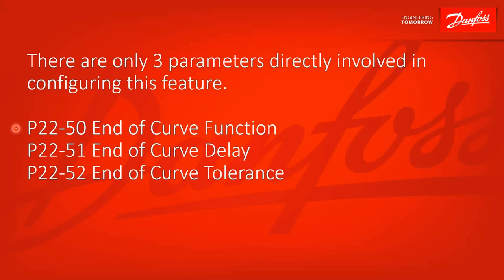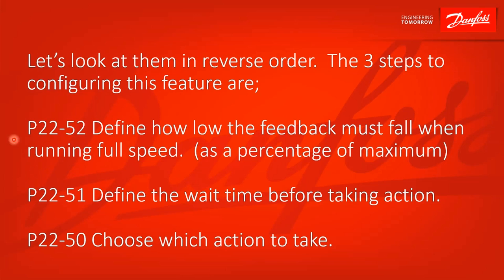You've got parameter 22-50, that's the end of curve function. What do you want the drive to do in this situation? Parameter 22-51 is the end of curve delay. How long do you want the drive to be in that condition before taking that action? And then 22-52 is the end of curve tolerance. How much below?